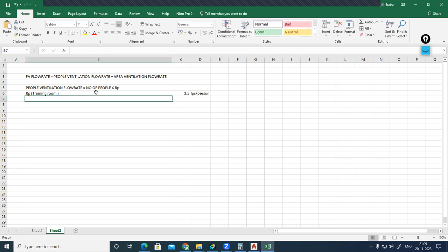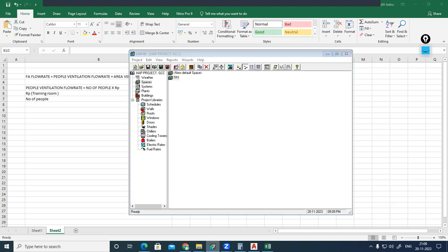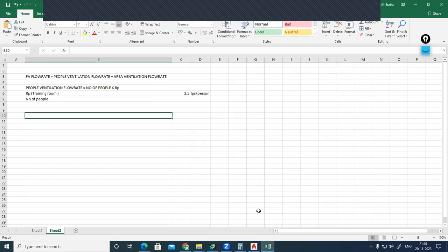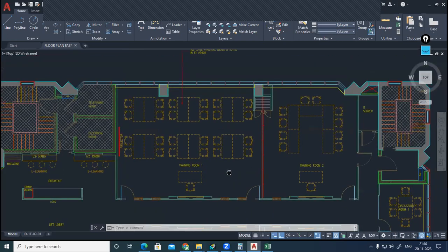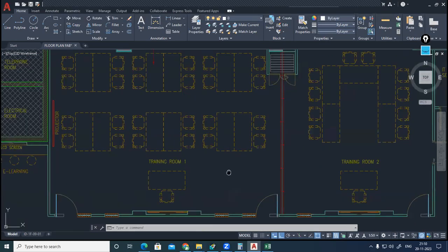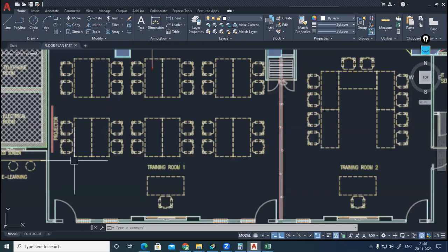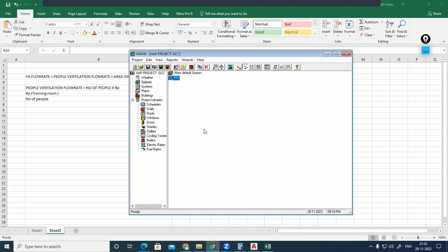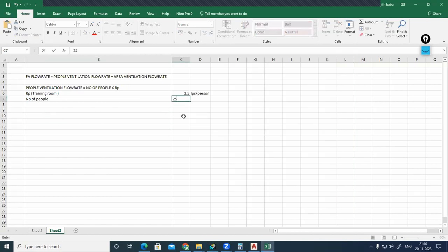So how many number of people will be there? So number of people also has to be calculated, right? So number of people will be, from where you can find number of people for time being. I will explain with respect to ASHRAE 62.1, we can calculate that. But for time being, already we are having a furniture layout. From the furniture layout, we can select. So inside this training room one, how many number of people are there? 1, 2, 3, 4. You can count the chairs. 1, 2, 3, 4. 1, 2, 3, 4, 5, 6. So 6 into 4, 24 plus 1, 25 number of people, correct. So here we are having 25 number of people. So number of people will be 25.